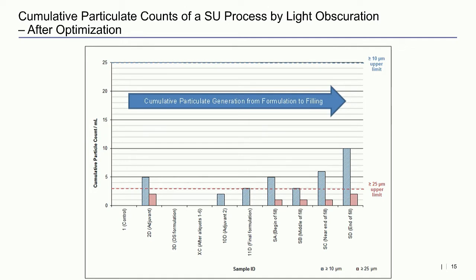The third problem was resolved with a combination of optimized pump head, tubing size, tension setting on the pump, and flow rate. With these changes and the study repeated, all the particulate results passed the USP criteria. It should be noticed that we can still see a small increasing count for both the 10 and 25 micron sizes observed during the filling process, which are the ones on the right. You can see an increase there.